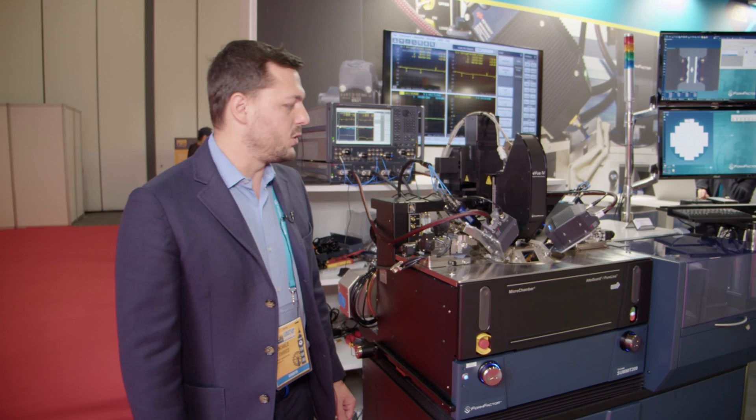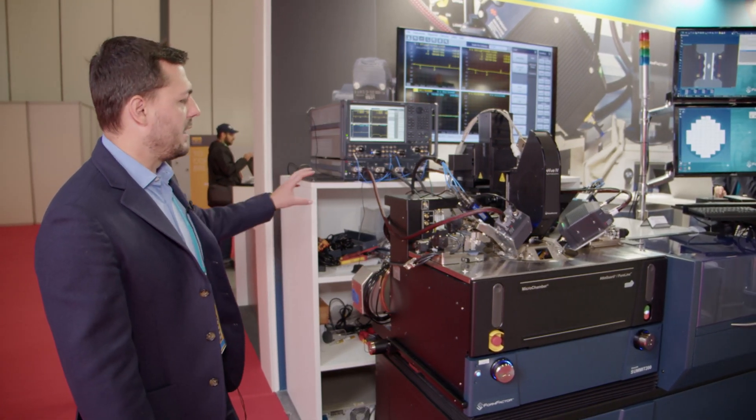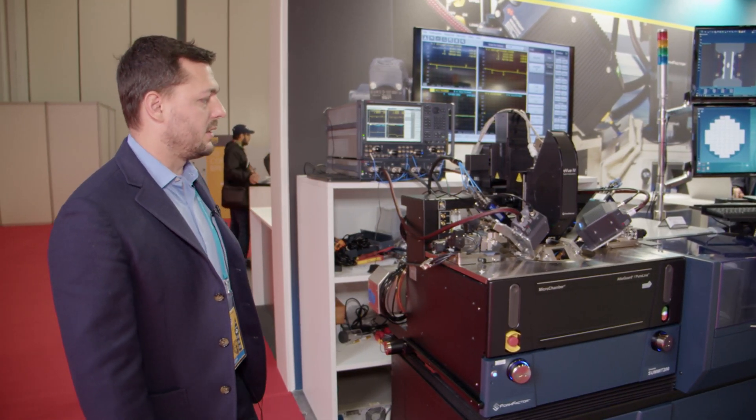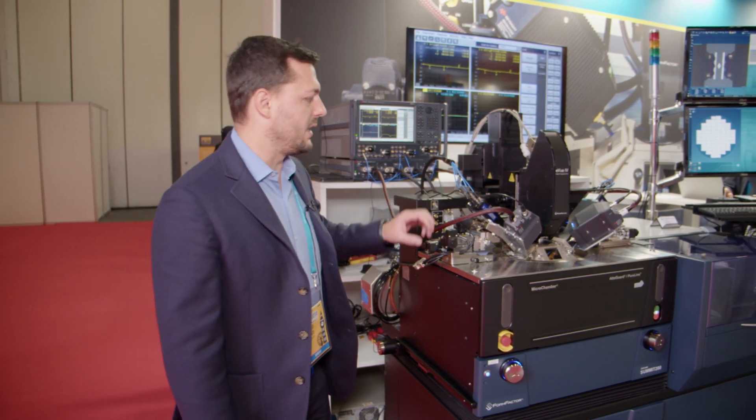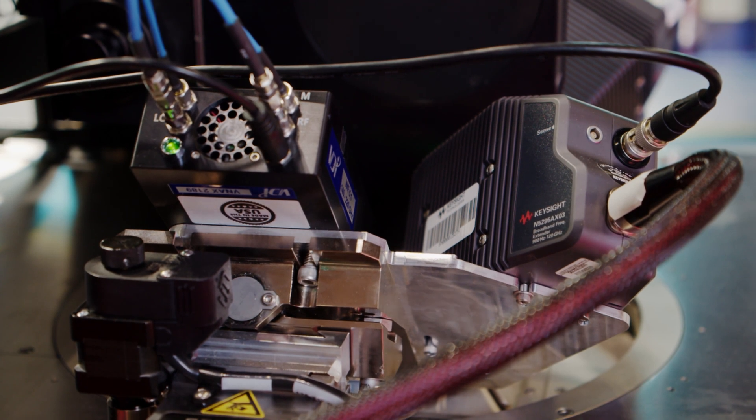I'm going to show you the different system-level components. Right here we have a Summit 200 millimeter probe station from FormFactor — it's a fully automated system, and it's controlled by the VNA. It's a Keysight PNAX, and that goes up to 67 gigahertz. There's a millimeter wave controller, four-port, that drives the two extenders: the Keysight N5291A system and the VDI frequency extenders as well.